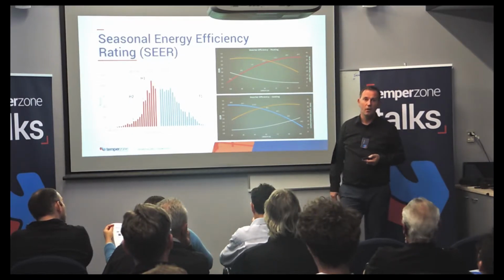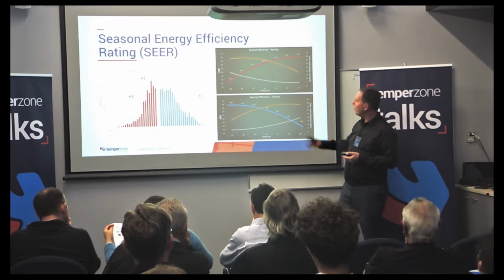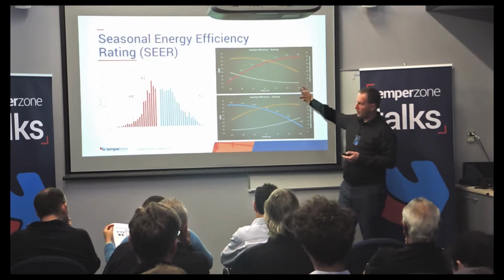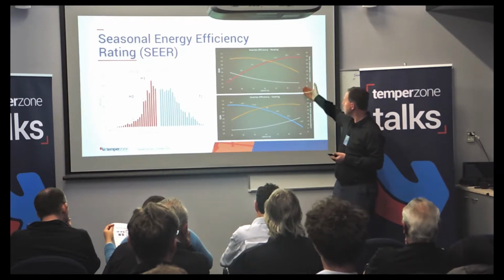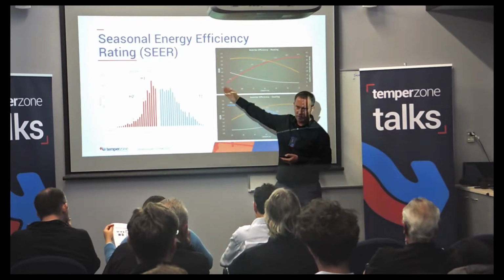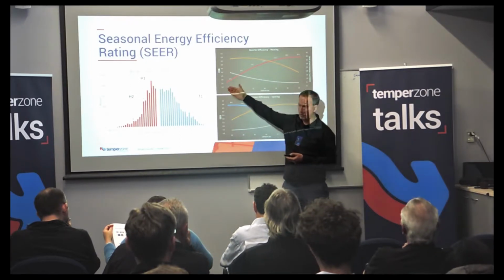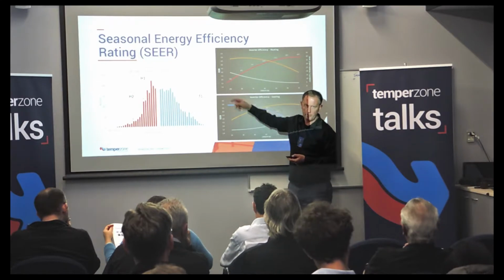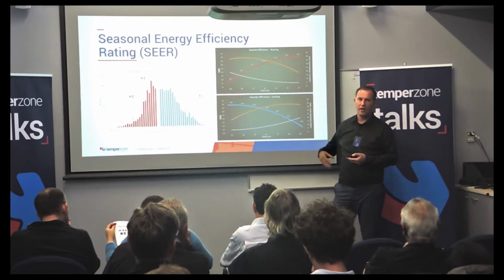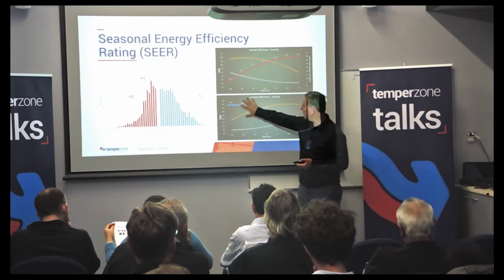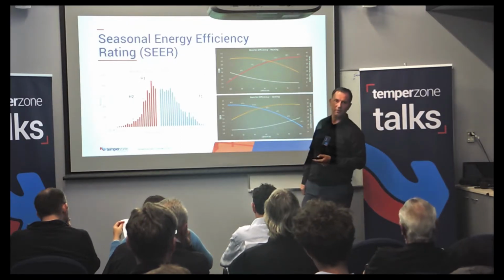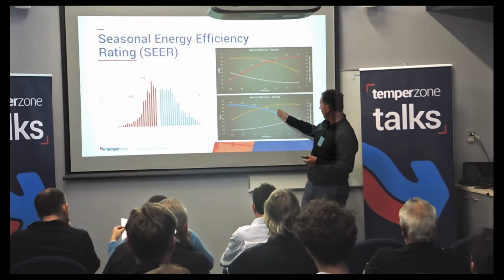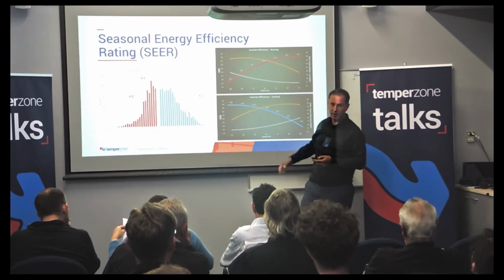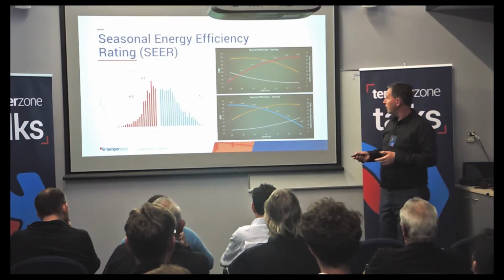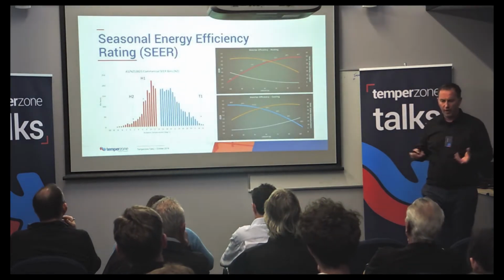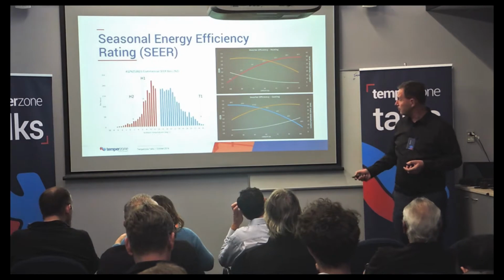Heating is exactly the same, but in converse to cooling. For convenience, I've swapped the capacity scale around the other way, so this time it's low capacity to high capacity. As it gets increasingly colder, the efficiency becomes lower. You can see that most of the time a variable speed system operates in these very mild conditions, not at all where the rating points are, which are here and here, so it very much drives us towards variable capacity systems.